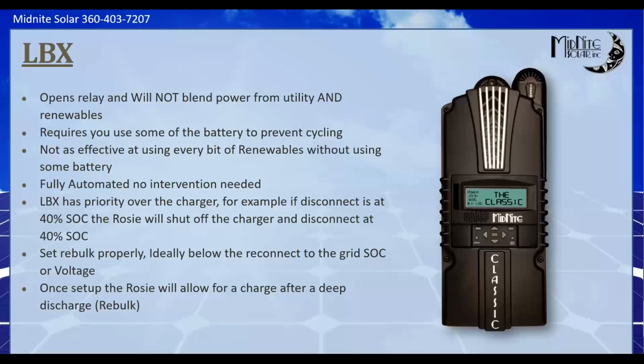so that we just stay disconnected and we're not transferring back and forth. So because of that, it may not be as effective at using every bit of renewables as grid support would be if you're trying to stay at a high state of charge. If you're trying to stay at a low state of charge, or if you're trying to drain the batteries down to like 50% every night, then it's a little easier to still use every bit of that. We talked about LBX does have priority over the charger. I think I explained that one. You set your rebulk ideally below the reconnect grid state of charge, but again, I recommend disabling the battery charger in LBX mode because it will actually start a charge when it connects.